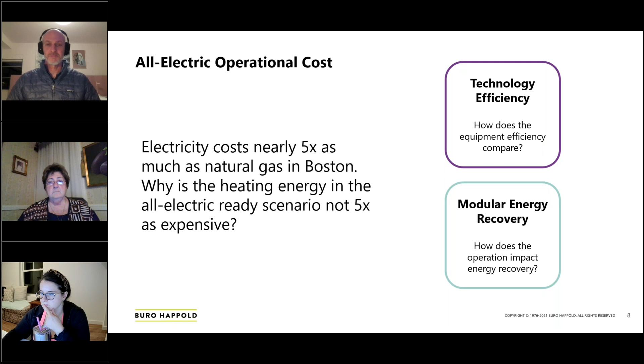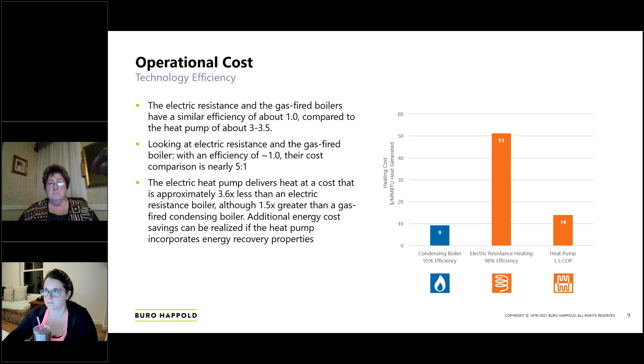And the main component that leads to that is the efficiency of a heat pump chiller, which is one of the main pieces of equipment providing heating. The efficiency of a heat pump chiller is much greater than that of an electric resistance boiler. So if you were to compare a gas-fired condensing boiler to an electric resistance boiler, that is where you would see the 5 times more expensive heat. Because of the efficiency of the heat pump chiller, that cost really does show a fairly significant decrease from that electric resistance, but still a slight penalty from the condensing boiler per unit of heat generated.